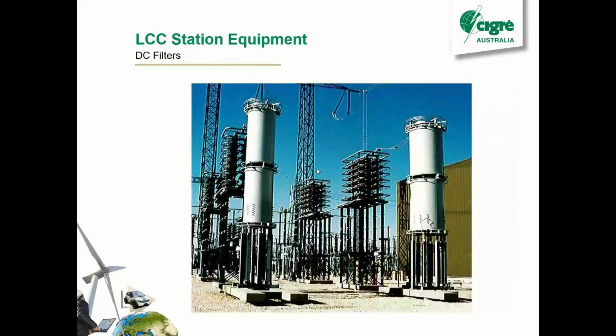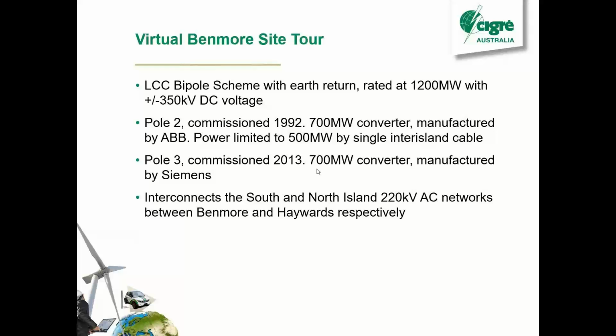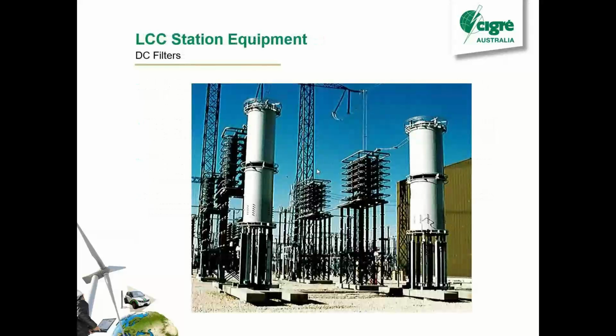And this is a DC filter. It's basically pretty similar in arrangement to the AC filter, except you're just going for those different harmonics. Another thing with the DC filter is that in a lot of schemes you don't actually have to have the DC filter in. We're able to operate without the DC filter on our scheme. We don't, but if we had a fault in it, we could switch it out and still operate. You can't do that with AC filters. AC filters are critical. It's sort of the Achilles heel of the LCC. If you have too many AC filter problems, you can severely limit the amount of power you can transfer.